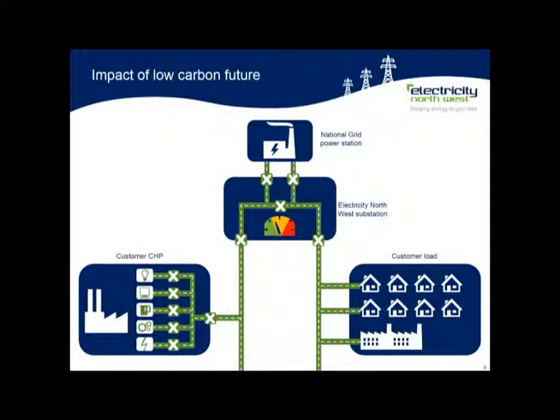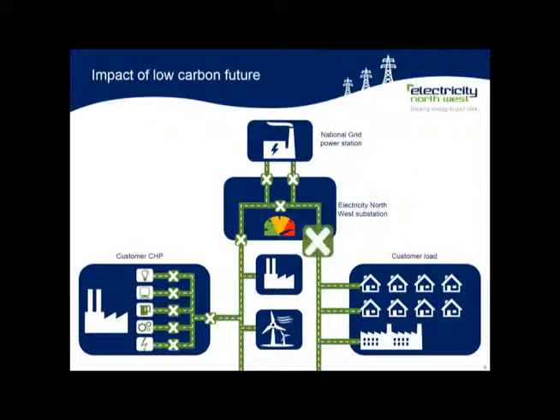In the future, as the number of low-carbon technologies on the network increases, particularly the number of generators, the circuit breaker in this example will need to deal with an increased amount of fault current. As the amount of potential fault current increases, the dial shown here moves from amber to red as the circuit breaker reaches its safe capacity. Historically, this would mean it would need to be replaced for a larger equivalent unit, which is both expensive, time-consuming and disruptive for customers.